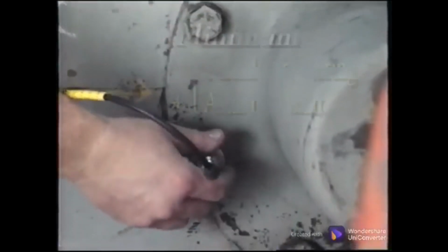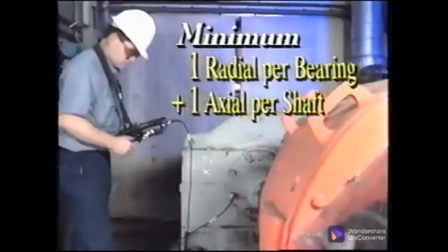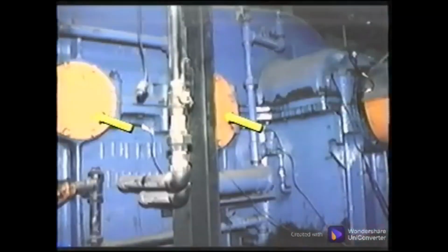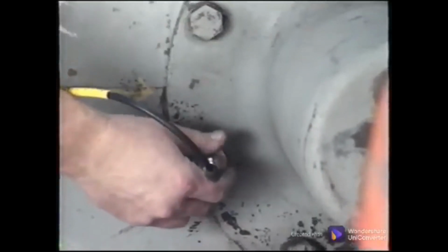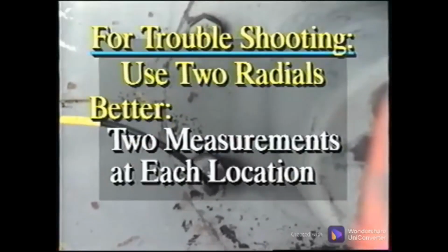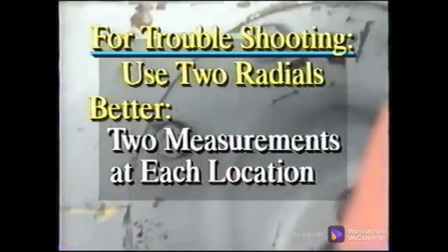Routine surveys for single reduction parallel shaft gearboxes require a minimum of 1 radial and 1 axial measurement at each bearing location. These panels are merely access panels and do not provide a solid path to any internal web. Do not make measurements on them. However, the bolts are usually good sources of transmission because the threads tend to lock onto the case and carry the frequencies well. Use 2 radial measurements when troubleshooting problems in a gearbox.